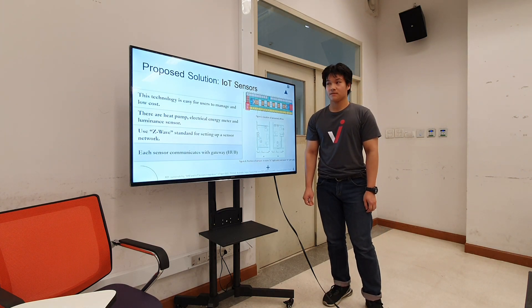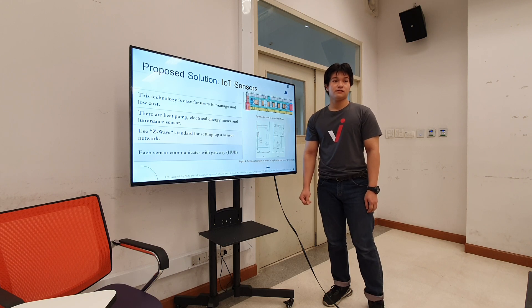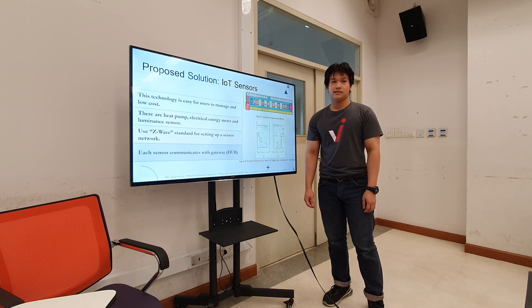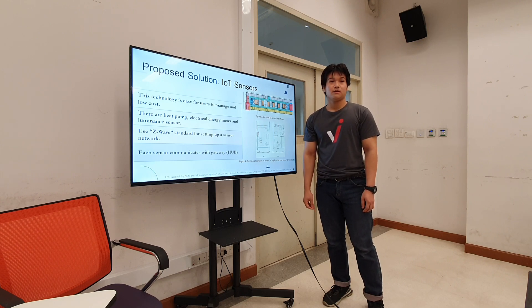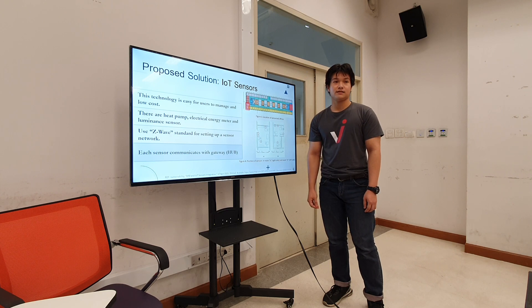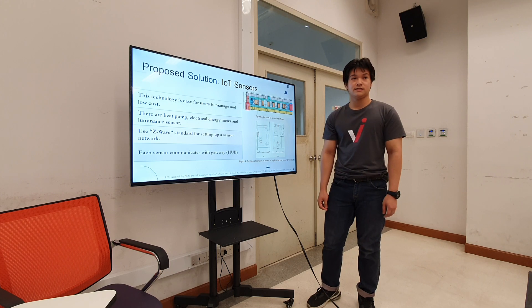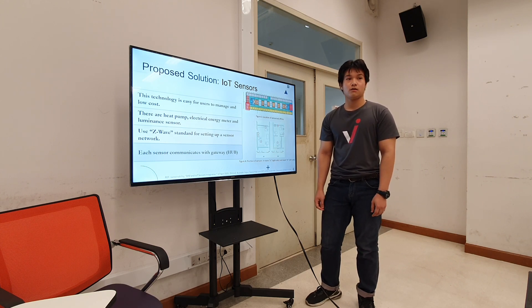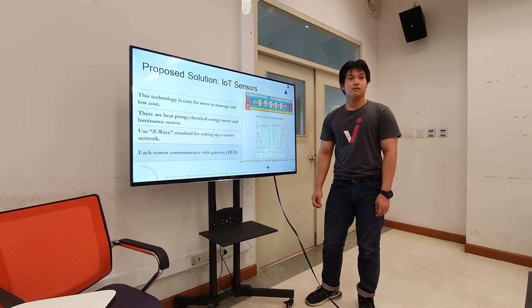Regarding IoT sensors: innovative IoT sensors are easy to manage for real-time measurement and monitoring of building environmental conditions and energy consumption. A radio standard called Z-wave is also used to set up a wireless sensor network. Z-wave has the advantage of using less energy, and the network becomes stronger depending on the number of devices. These devices communicate with a central device called a controller or gateway, which sends data from the sensors to the IoT platform.